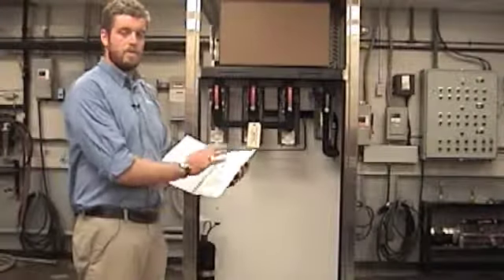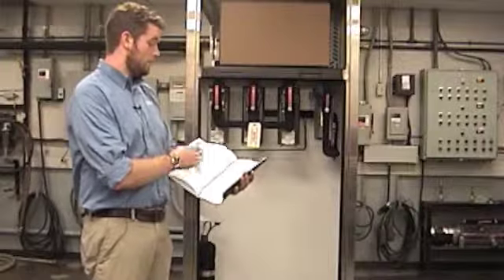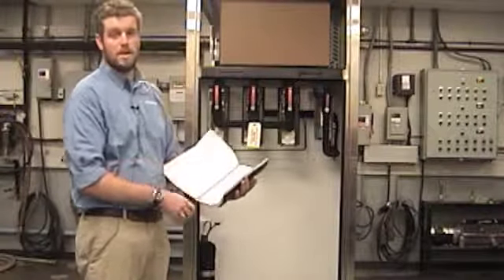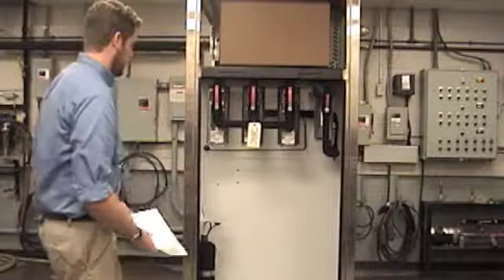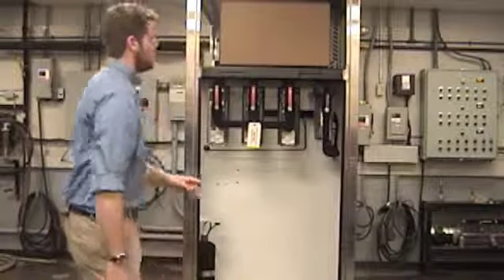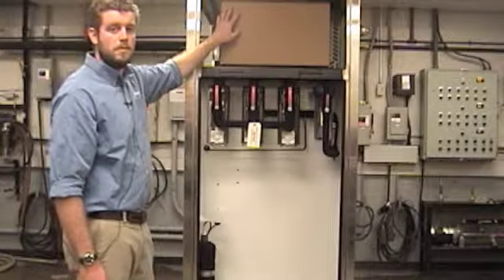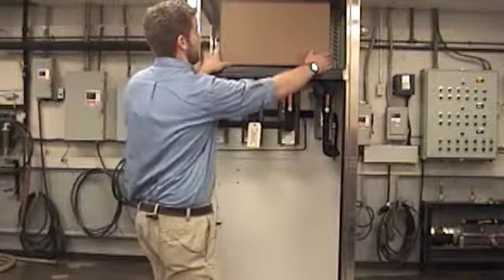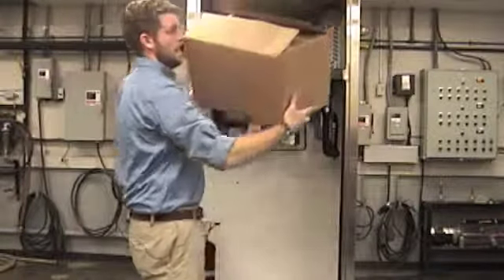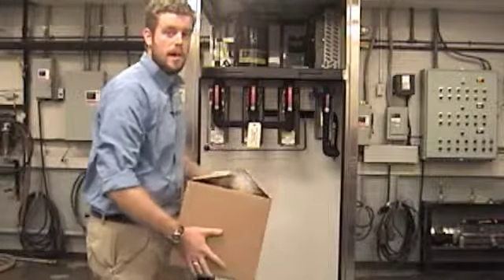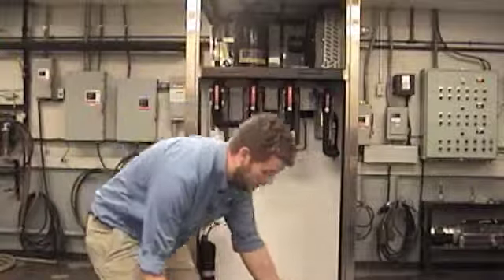Additionally, your manual will have your scheduled maintenance documents and how to perform maintenance on the unit. Each chiller is going to ship with a year's worth of consumables for your annual maintenance. It should be in a box somewhere inside the chiller cabinet. When you remove the panels, you'll be able to see it.